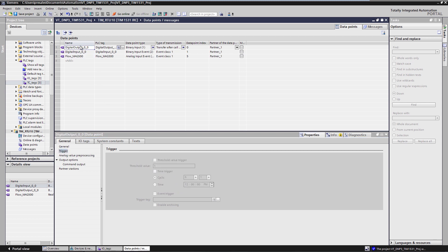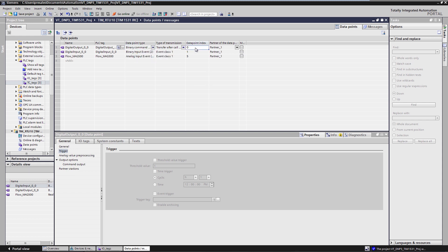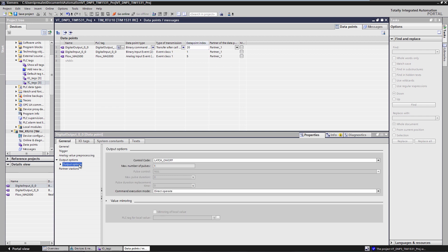Finally, I configure the command that we receive from the control center. We receive a command, object group 12 variation 1 on DNP3 address index 20. We still need to set the exact type of command when receiving a command, for example, whether we receive a so-called latch on latch off or a pulse command.